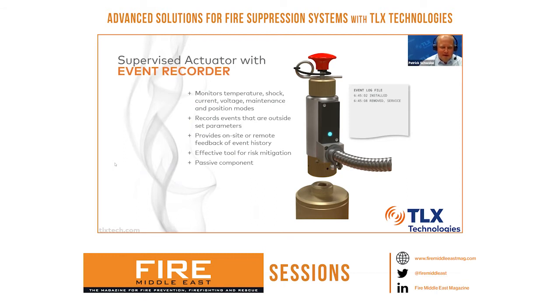This device itself is a passive device, so you can't fire the device wirelessly, and you can't fire the device remotely. It's still only fired by the electrical signal from the panel. So the component is just monitoring the system. This device can be integrated into the family of linear actuators, so anywhere from the 25, 80 bar, to the 300 bar actuator, this device could fit on there.